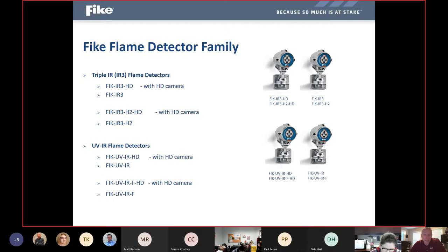into those detectors. So that camera does not have to be connected to a network, but it's built in on board and has its own little onboard memory, so that with traditional flame detectors, if it ever went into alarm, it would just trip the contacts on the back and annunciate to the fire alarm panel, but you would never know exactly what set that detector off. And so there were a lot of false alarms or false activations associated with flame detectors in the past, because maybe by the time somebody gets out there to where that flame detector is, there's nothing going on. And so you don't know what set that detector off.